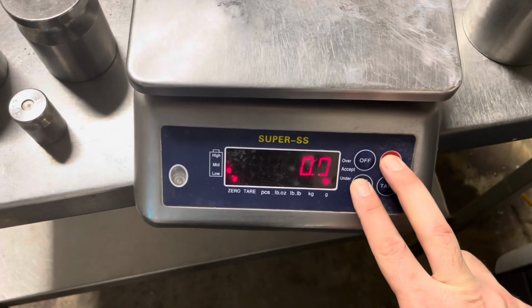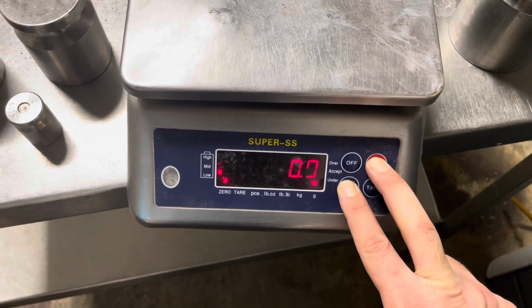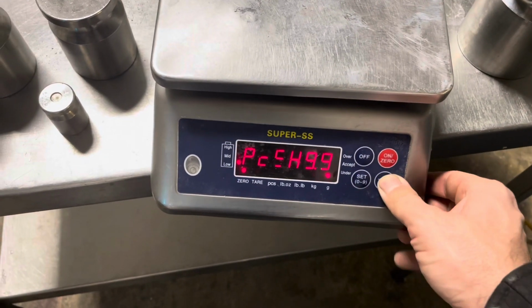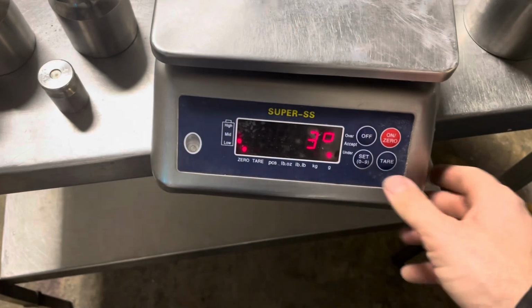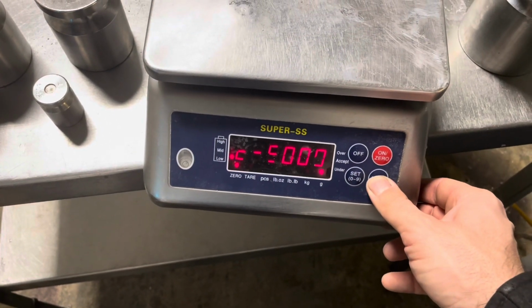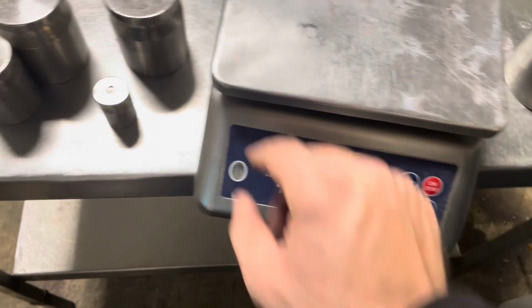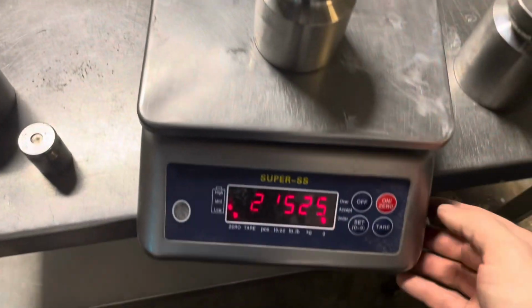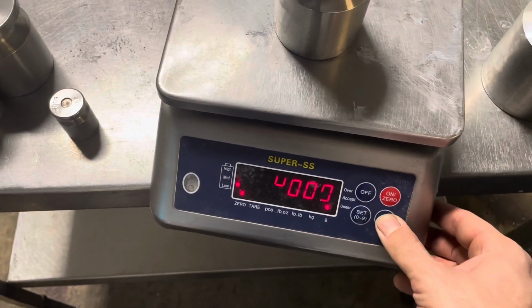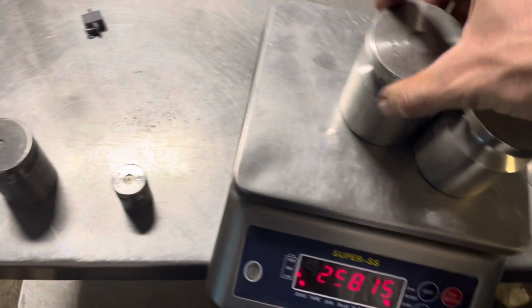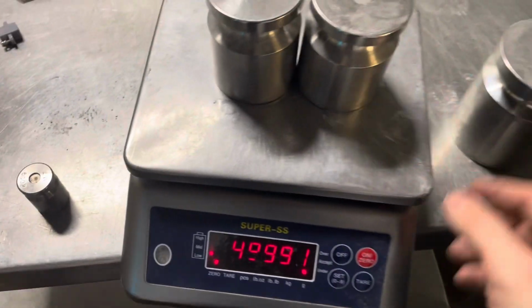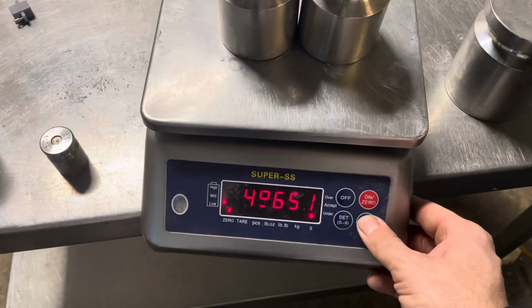So now we flip it up to in a calibration mode, and you'll see a 3P, as in 3 points. This actually allows the scale to weigh accurately. So we do the single point. It's a 6 kg capacity scale, 2 kgs each time, so 2 kgs, then 4 kgs, and then the ending of 6 kgs, at which point the scale will be accurate.